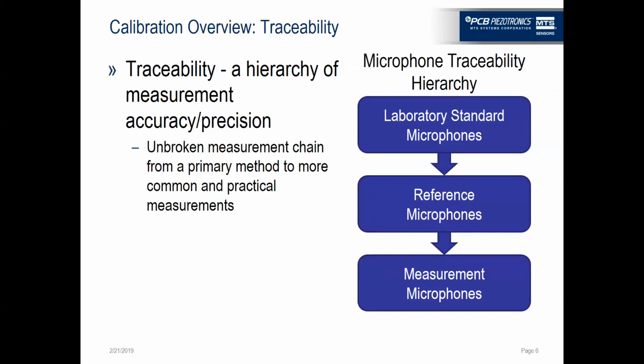And it's very important to note that whatever laboratory you're using must have some reference or some way to get a reference back to a laboratory standard or to primary calibration. Otherwise, you don't know the accuracy of your measurements or of your calibrations from that laboratory.